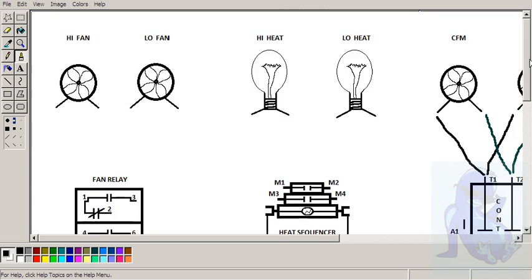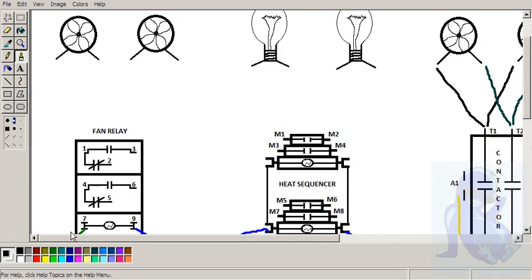So we need some high voltage to our fan, and we need high voltage going into the relay. This is the point where high voltage goes in, terminal 1, and this is going to go back to...